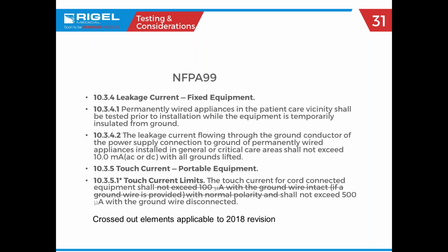So another kind of busy slide. So basically, this is just an excerpt from the NFPA 99 standards regarding your fixed equipment. So that equipment that's hardwired directly into the facility. And you can see here that the reading must be less than 10 milliamps, and that's AC or DC, with all of the grounds lifted. And I've scratched out the portion at the end that was changed in the 2018 revisions. So with that change, portable equipment, the reading should not exceed 500 microamps with the ground wire disconnected. And so that just makes your life a little bit easier now that they've cut out some of those tests as well.